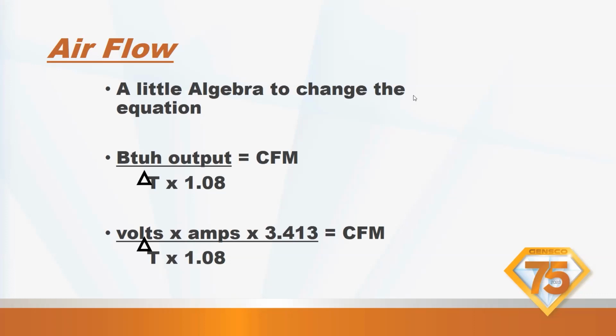So you're going to take the temperature rise across the furnace. You're going to check the BTU output of your gas valve. So say you have a 100,000 BTU furnace at 95% efficiency, it's 95,000 BTUs. So 95,000 divided by your delta T times 1.08 equals the CFM. That's for a gas furnace.